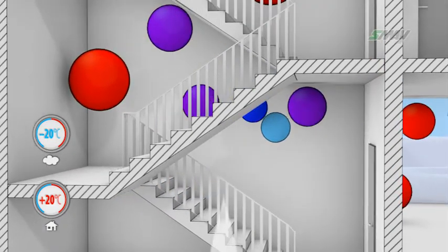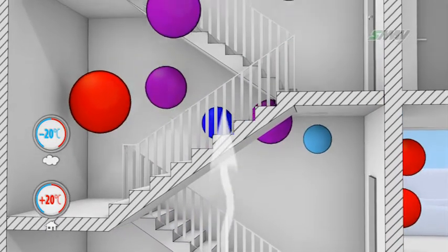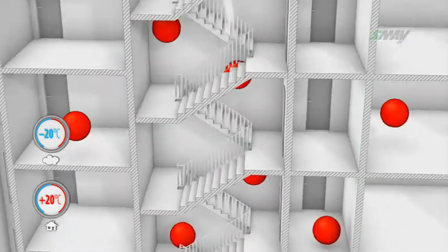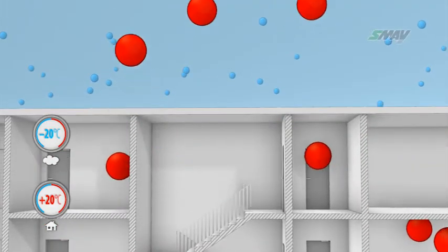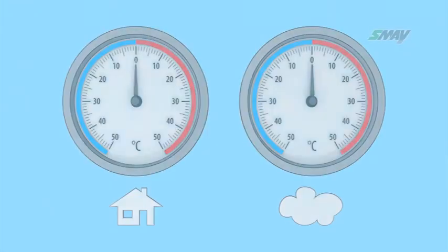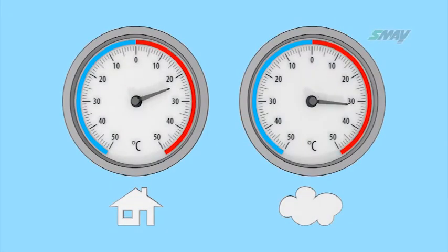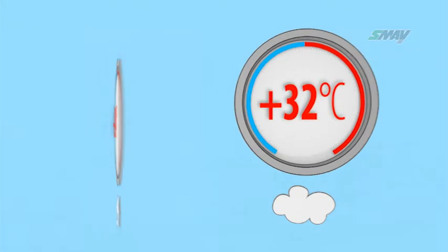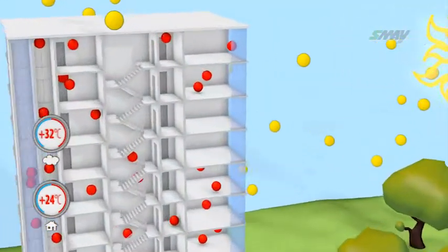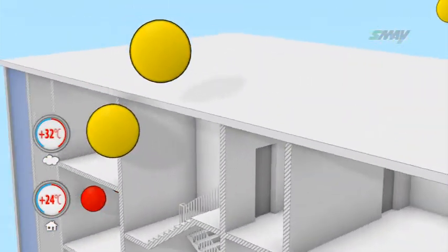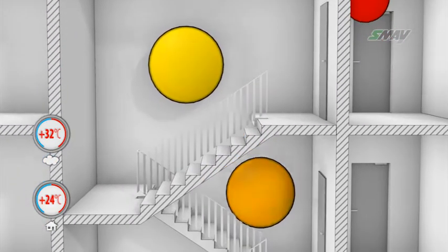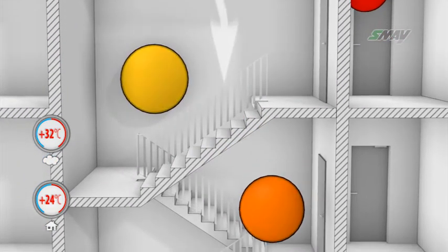The stack effect will always occur if there is a difference in the air temperature between the stairwell and outside. In summer, on the other hand, the hot air from outside seeps in through fissures into the stairwell, cools down and falls, resulting in a pressure distribution opposite to that which can be observed in winter.